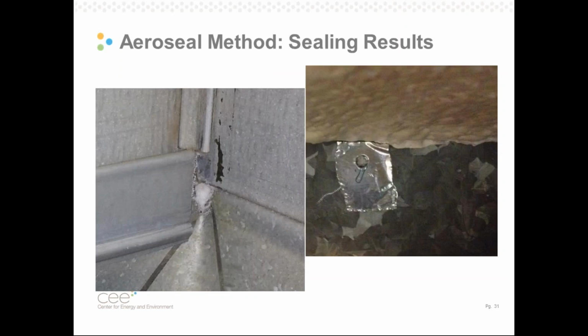Aerosol sealant, using the Aeroseal method, is a little bit trickier to see. We find that you don't really find it anywhere because it tends to deposit only on the leaks. And most of the leaks in these duct systems are actually invisible. They're buried in the twists and bends of this sheet metal.